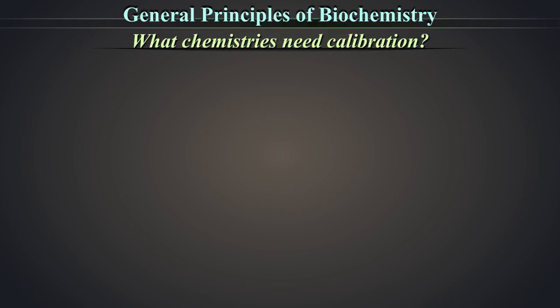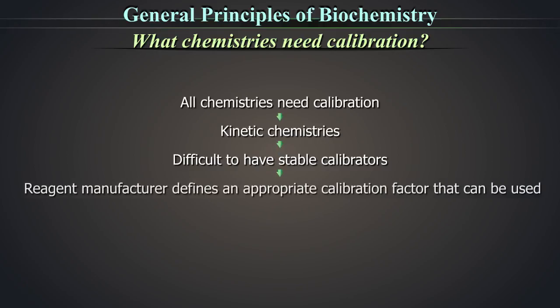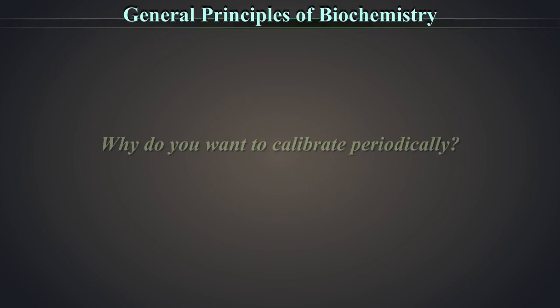What chemistries need calibration? All chemistries need calibration. However, for certain chemistries like kinetic chemistries, it is difficult to have stable calibrators and so the analytical system defines an appropriate calibration factor that can be used. This needs verification with QC every day.